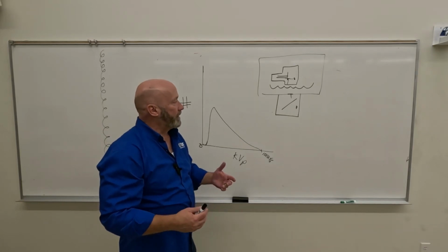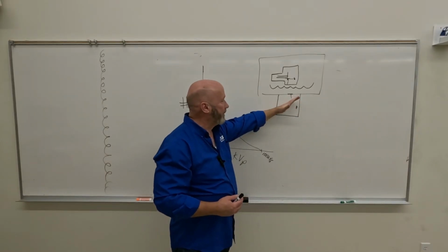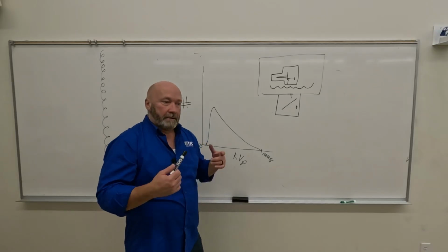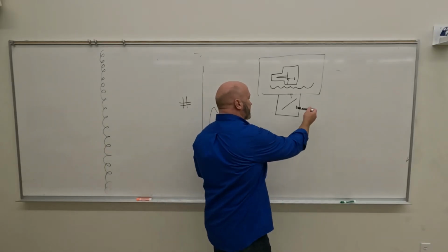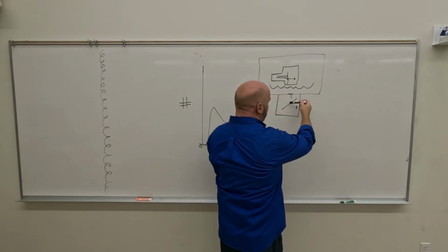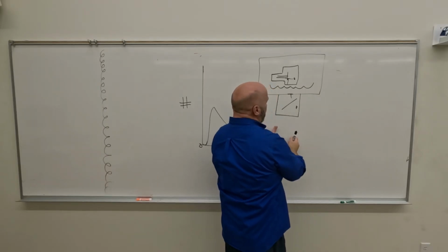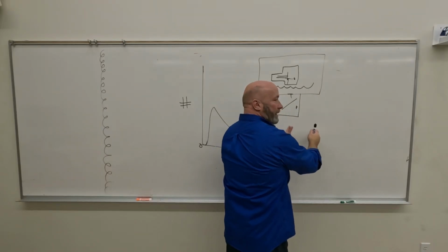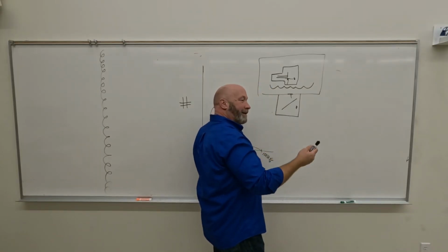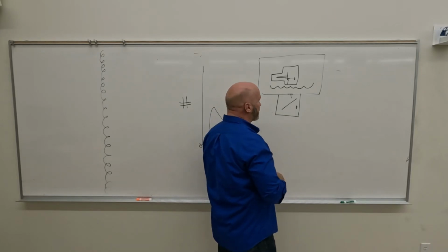So the thing about the collimator, the mirror and the collimator housing, is the mirror has to be mounted at a specific angle, and that's 45 degrees. The reason it's got to be at 45 degrees is because the stream of photons would still be coming straight down, but if it was at any other angulation, the light would be reflected somewhere else. It's got to be a perfect 45-degree angle. So what might cause that angle to fail? Well, you bang it around a tube, so be careful with the tube.